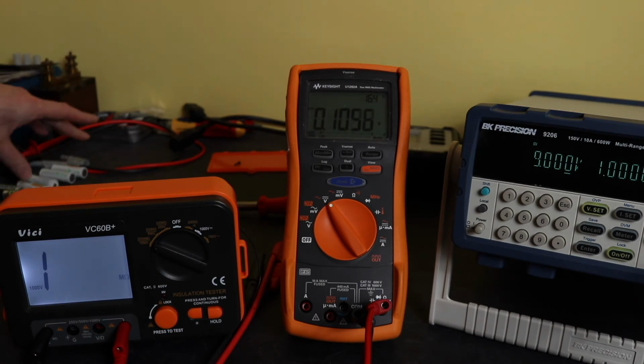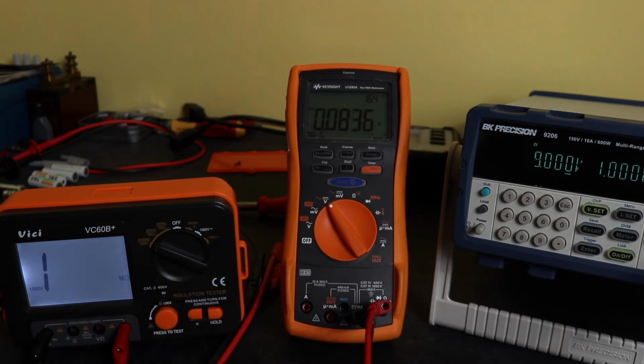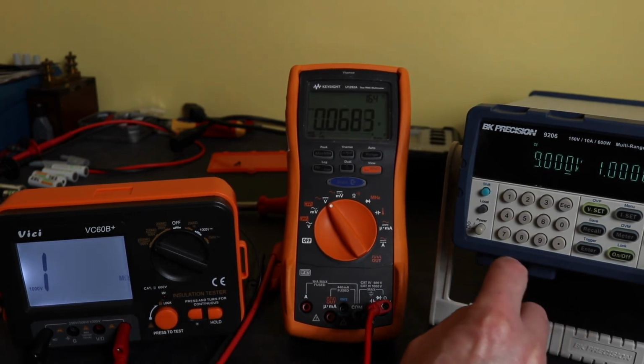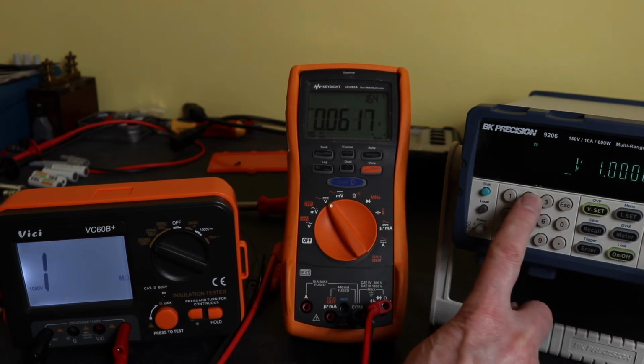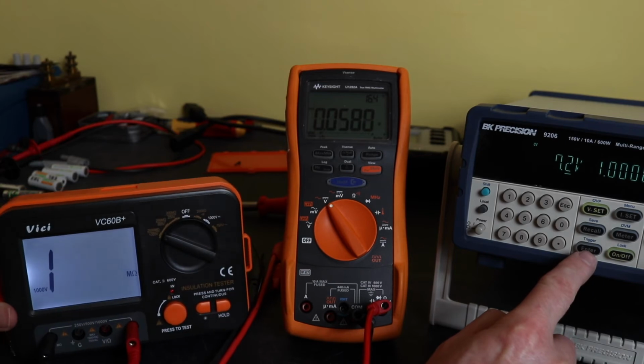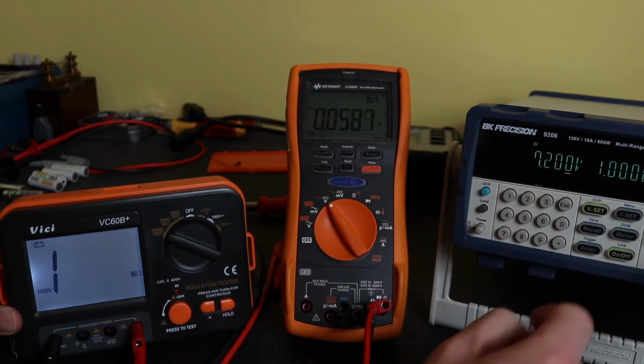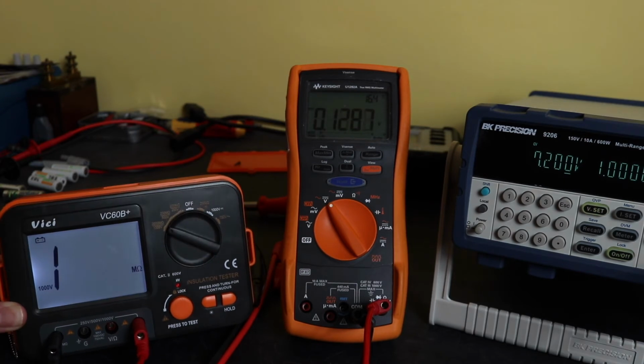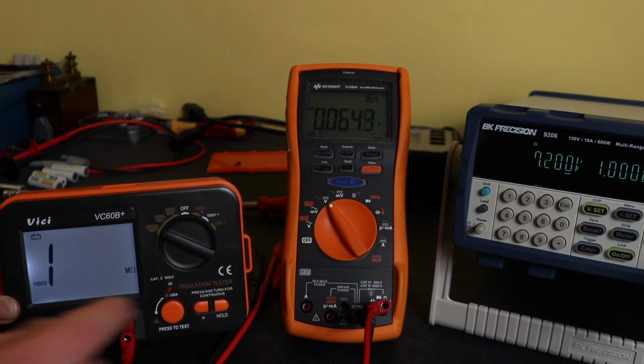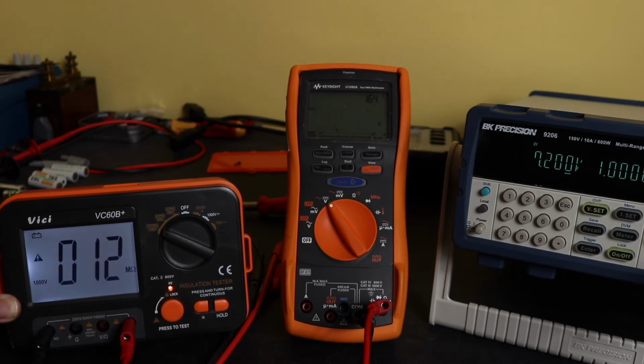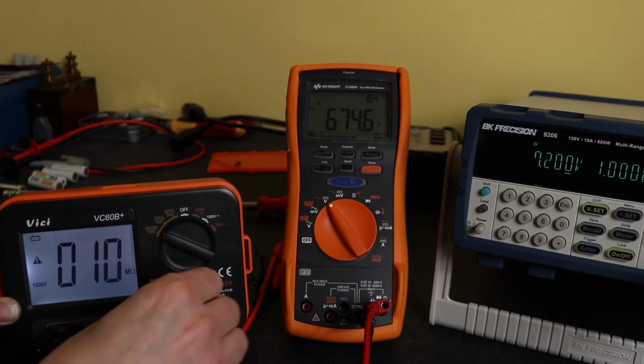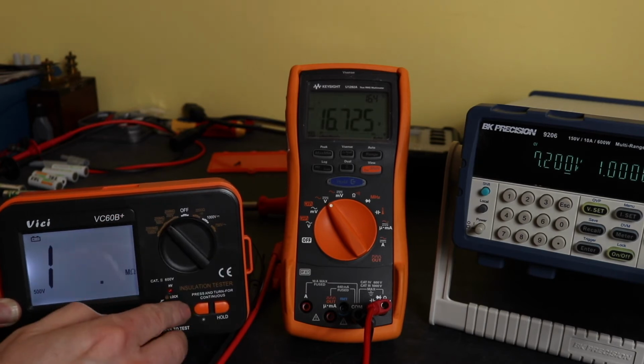Nominal voltage on these is 1.2 volts, and I've never had a problem with any other insulation tester using those kind of cells. So 6 times 1.2 volts will take you to 7.2 volts, which we can set here on the supply. And if we watch the display, enter, you can see immediately low voltage signal is coming in. And if I go for the test now, I'll do it at 1000 volts. We're now down to 674 volts. And all these ranges drop accordingly.